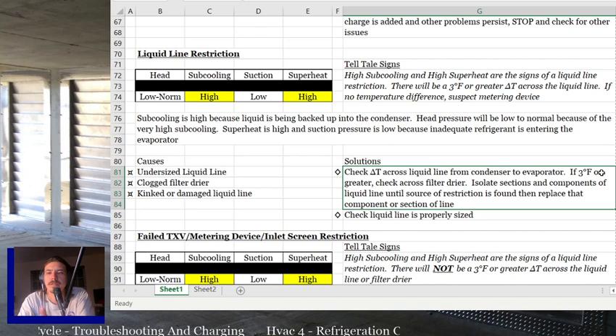Is it in the line set between where it goes in the house and the evaporator, where it's inside the wall? Did it get kinked there? Is it right there at the filter dryer? Is it somewhere else? Try and isolate sections until you figure out where that 3 degree temperature drop is happening, and then check that the liquid line is properly sized.